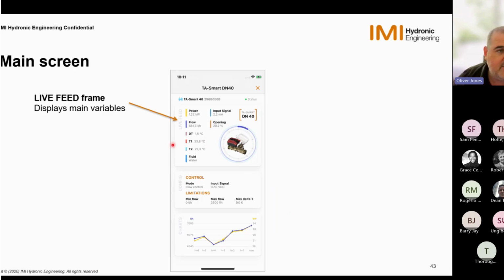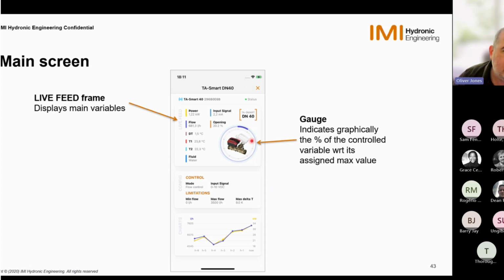So this is displaying our delta T, our current temperatures, flow and return, the fluid. So if it's water or if we've set it to be with glycol and what percentage, we can see our flow, our input signal, and then the opening as well. And then this is our gauge. So this is showing the indication of where the percentage of where the valve is being controlled currently with regard to its assigned maximum value.